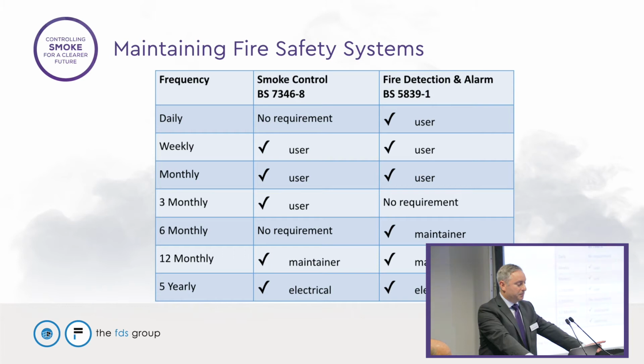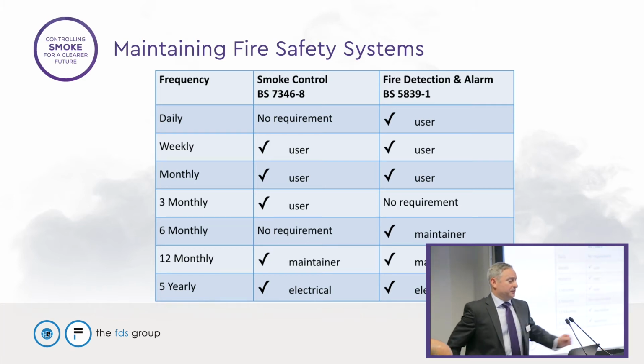But the most comprehensive one is the 3 monthly test, where over a 3-month period we're actually looking to confirm that every zone throughout the entire building has been operated. So this is non-intrusive testing done by the user, which could be your facilities management company, the premises management company, the concierge. It's not a skilled role, but it's something that should be done by a person who's been briefed and informed. Notice there's no requirement for fire alarm systems there.